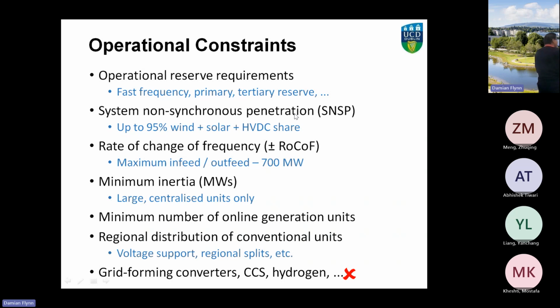New plans for interconnection with France will actually increase the size of the largest in-feed, and that causes stability concerns. If you have all of that wind and solar on the system, you begin to think about the conventional units: how many do you need, and where should they be in order to support the voltage and the fault level in the system?